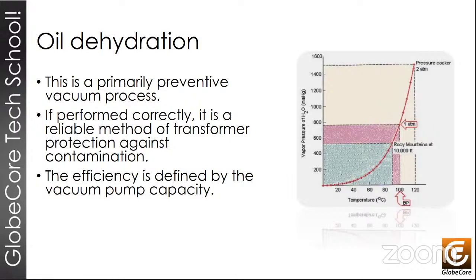Oil dehydration is a relatively straightforward process. It's commonly used with vacuum. We know that the boiling point of water is 100 degrees centigrade at the pressure of 1 atmosphere. So now we can see in this graph that if we're in the Rocky Mountains, for example, at about 10,000 feet of altitude, the boiling temperature of water drops to 90 degrees. This is due to the atmospheric pressure, because at high altitudes the pressure is lower, and that makes water much easier to evaporate. And this is the principle used in all thermal vacuum processes. It's a tool that allows us to safely extract water from oil. So we can see it in this graph. Next slide, please.